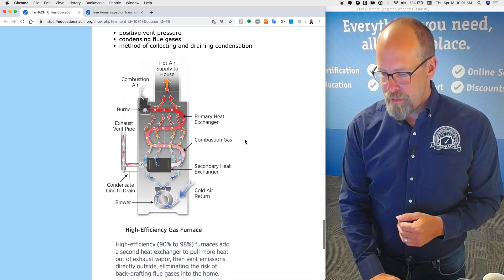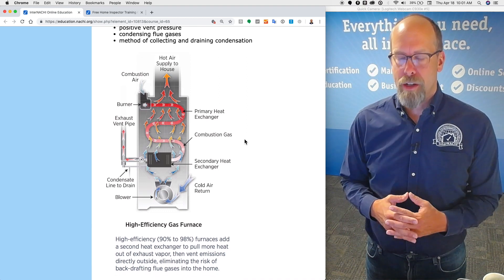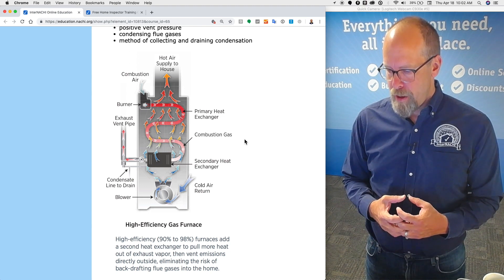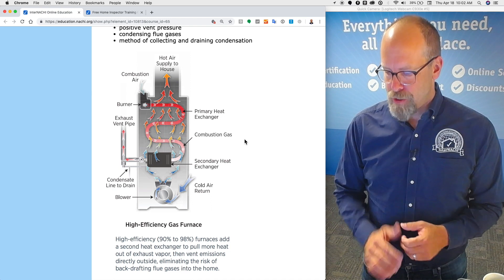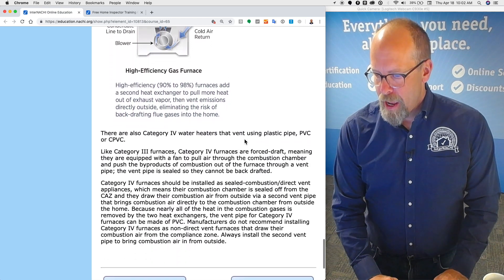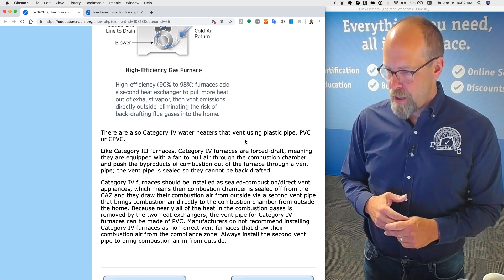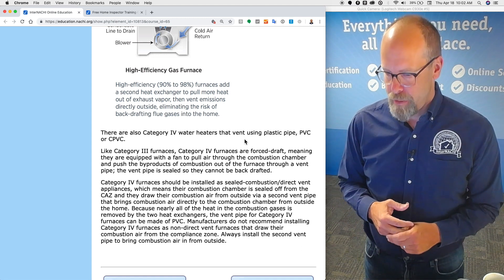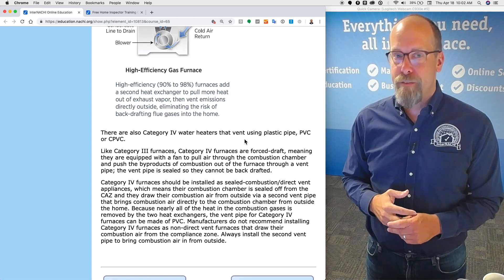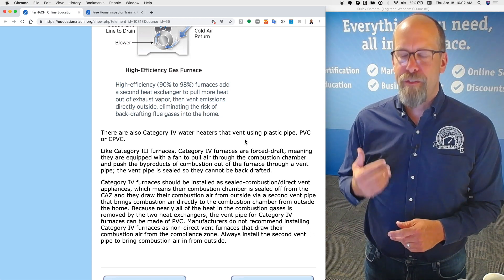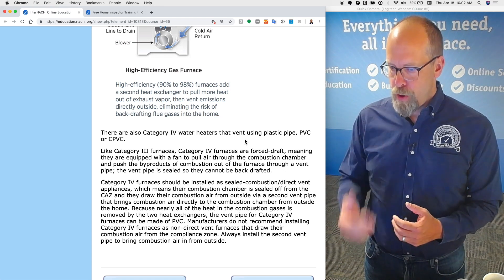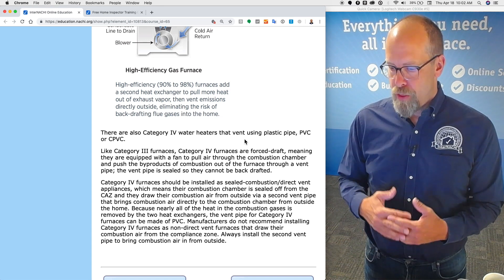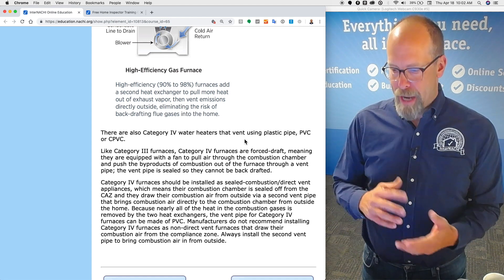High efficiency, 90 to 98 percent furnaces add a secondary heat exchanger to pull more heat out of the exhaust vapor, and then vent emissions directly outside, eliminating the risk of backdrafting flue gases into the home. There are also category four water heaters that vent using plastic pipe, PVC or CPVC. Like category three furnaces, category four furnaces are forced draft, meaning they are equipped with a fan to pull air through the combustion chamber and push the byproducts of combustion out of the furnace through a vent pipe, and the vent pipe is sealed so that they cannot backdraft.